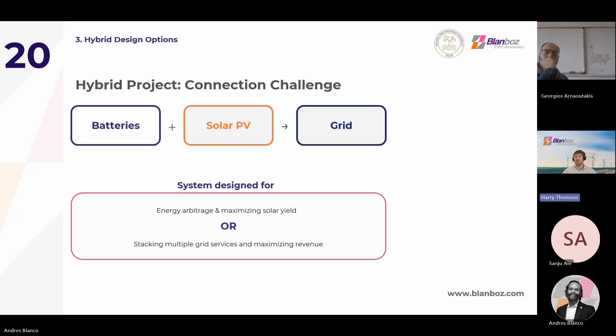choice. So we have our battery, solar, and a grid connection. How are we going to electrically connect them? The primary choice for this is the use case of the battery. Is the system designed to maximize the solar generation and provide energy arbitrage to the grid? Or is it to deliver grid services, stabilize the grid through efforts such as frequency response and reactive power, and maximize the possible revenue streams?